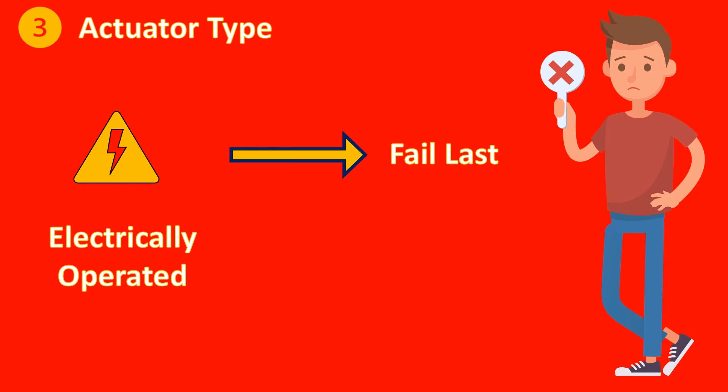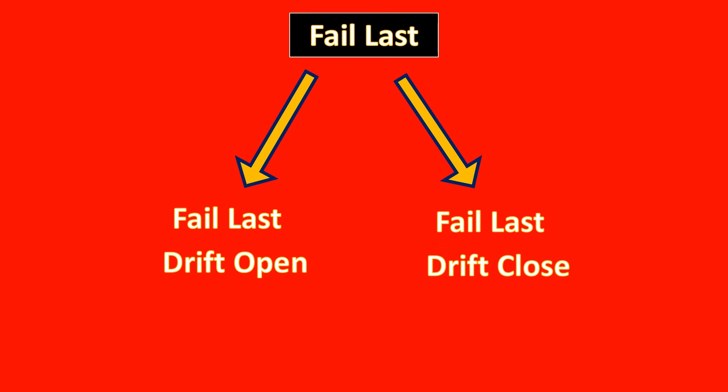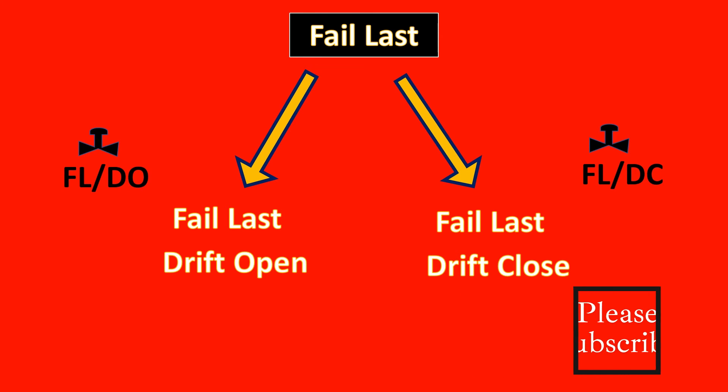An electrically operated valve usually has the failure mode as fail last. Now this is not only sufficient to mention fail last. Why? Let us look at that. Fail last is further divided into fail last drift open and fail last drift close, with an example in PIDs like FLDO and FLDC. Let us understand this amazing example.